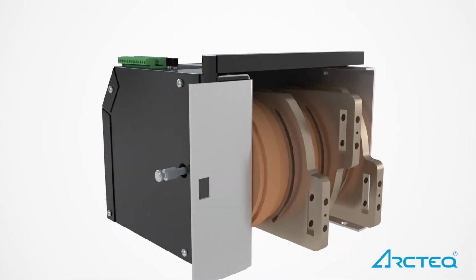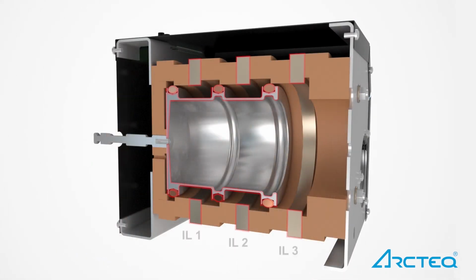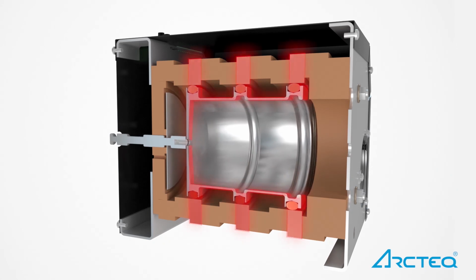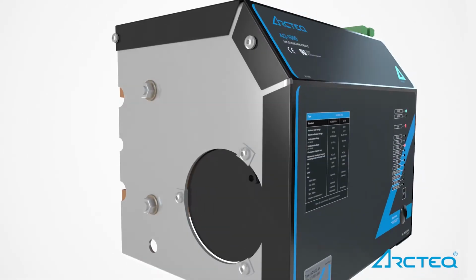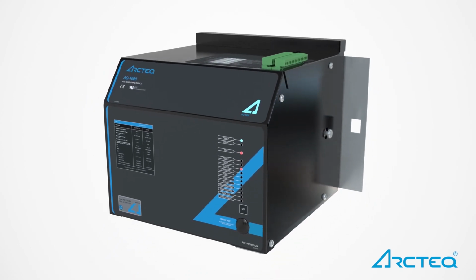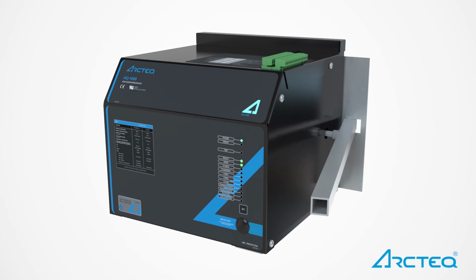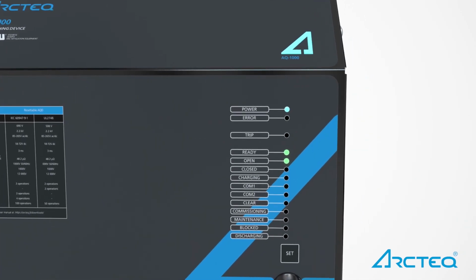The AQ1000 operation is based on patented and dependable Thomson coil technology. The bulletproof mechanism operating time is as little as 2 milliseconds. The use of Thomson coil technology makes the AQ1000 fully reusable and testable. The system can be conveniently reset after factory or site testing. Embedded electronics provide for full system self-supervision and operator status indications.